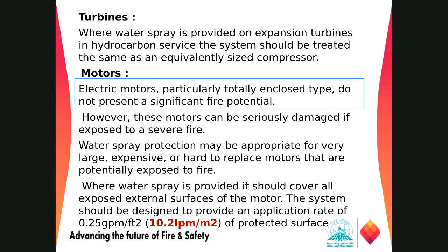In some areas the motor is of very high cost, very expensive or hard to replace, and potentially exposed to fire. So keeping that in mind, we need exposure protection for the motor also. And if we provide the water spray system in those areas, the system should be designed to provide a minimum density rate of 0.25 GPM per square foot of protected surface.